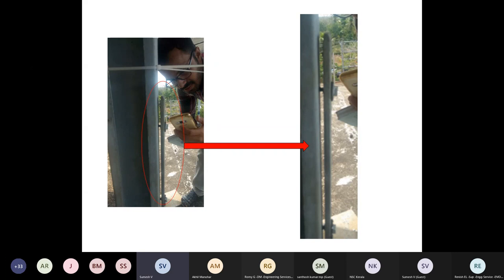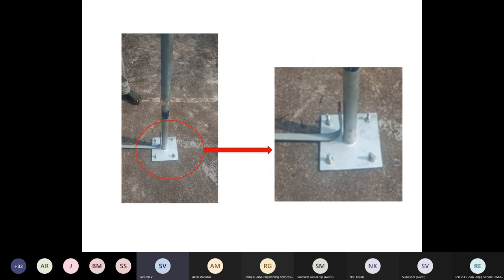Then the third photo, this is the foot of the lightning arrester. That pipe is carrying the lightning arrester, and that earth strip is used to connect the lightning arrester to the main earthing system. But he forgot to weld or screw the earth bar to the lightning arrester. When we asked, he said that the wire of the welding set and the driller is too short, so he could not bring those equipments near to that point. And he didn't expect that somebody would see this. That is the reason he gave when we inquired why he did it like this. So here the consumer has invested a lot in the earthing system, but he will not get its output when it is required. So all the consumers, all the persons should ensure that earthing is done in a perfect way.